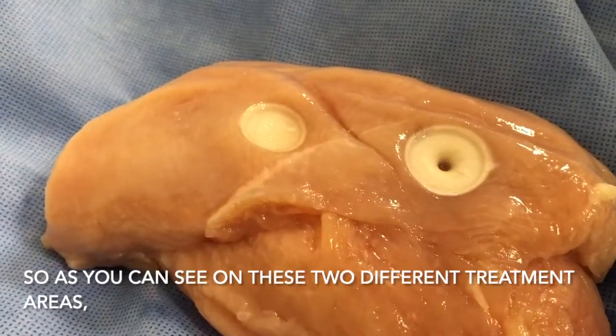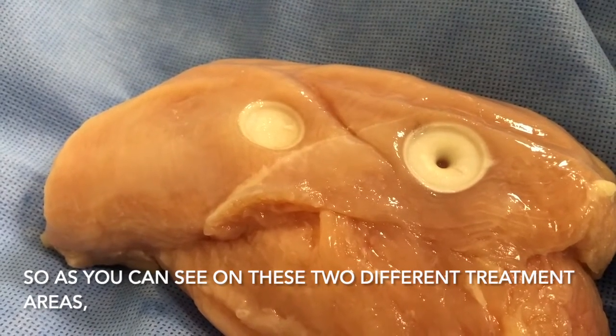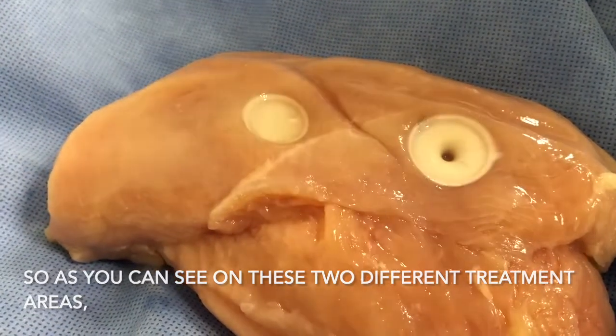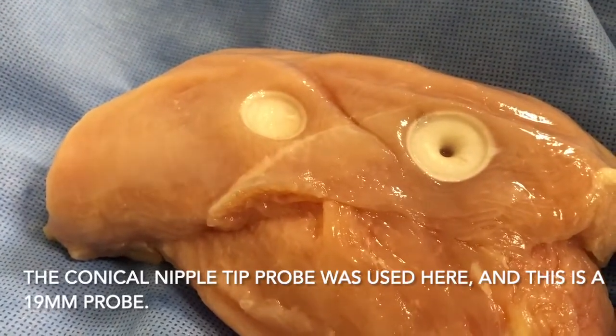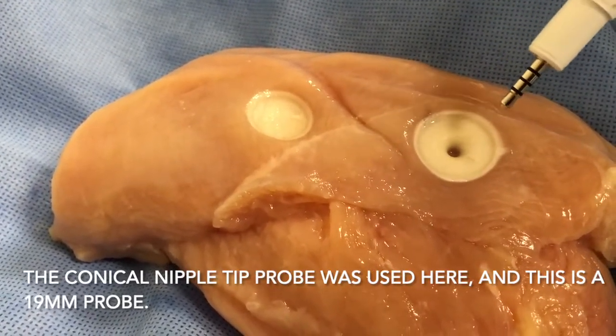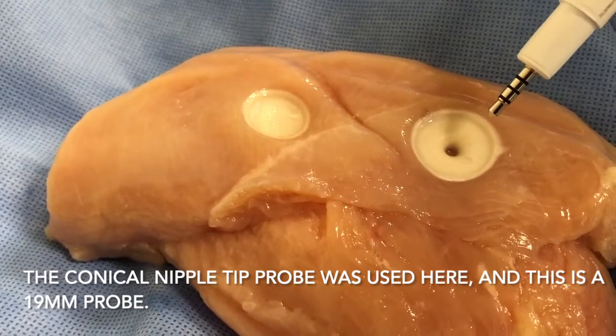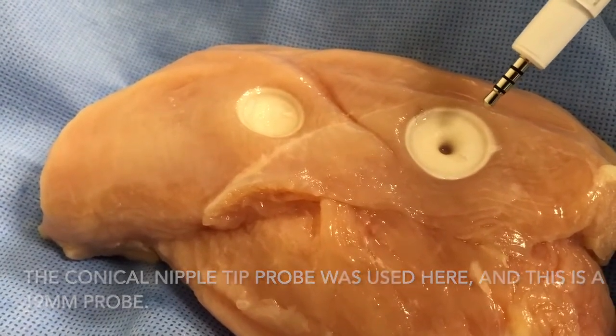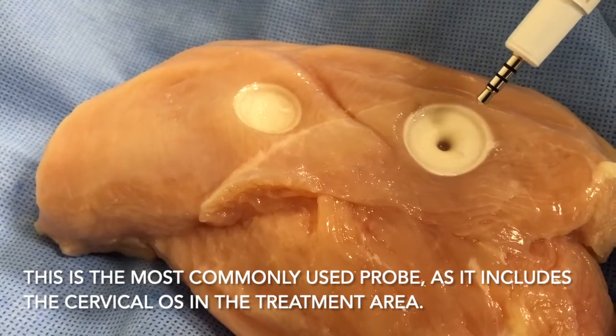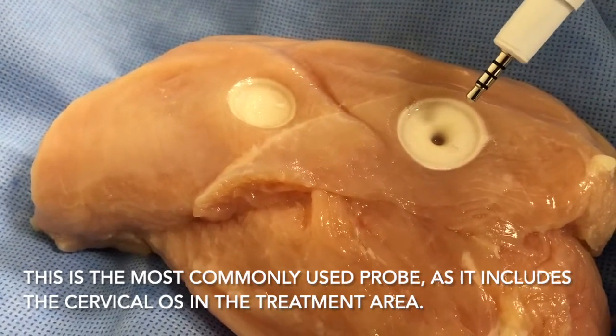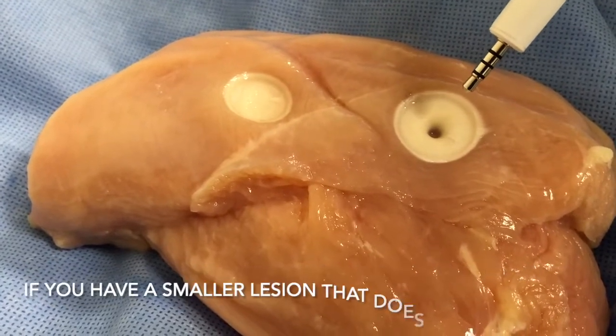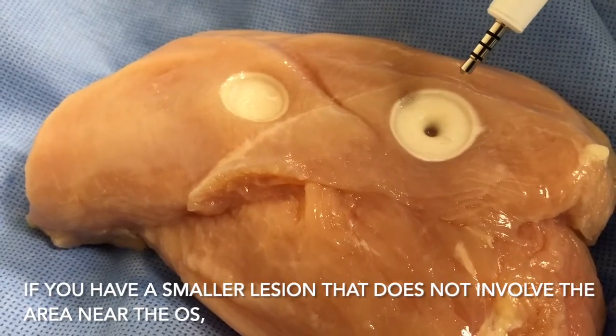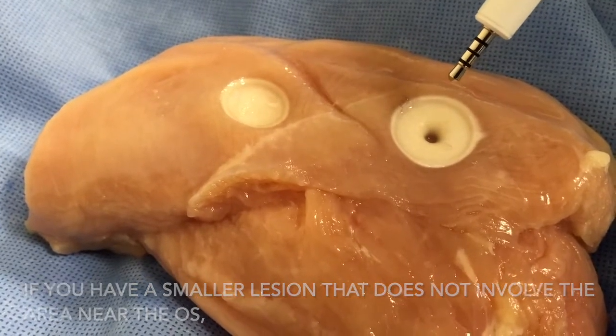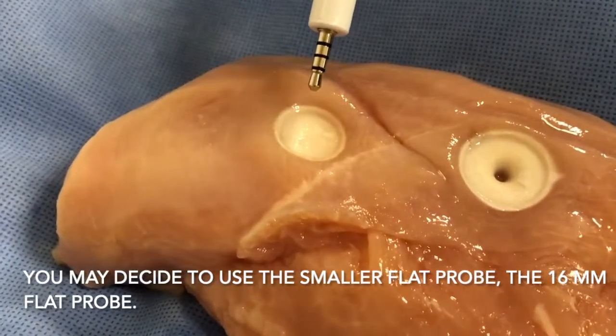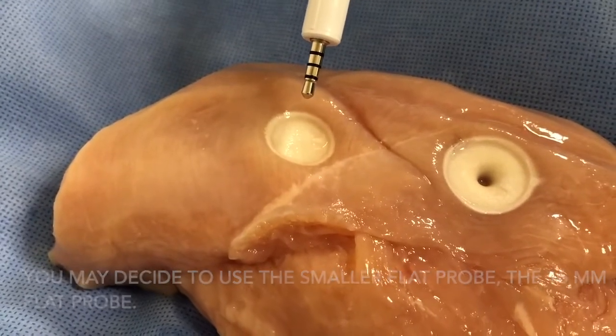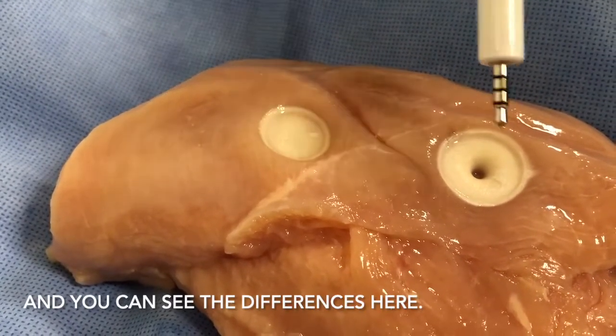So as you can see on these two different treatment areas, the conical nipple tip probe was used here, and this was a 19 millimeter probe. Again, this is the most commonly used probe as it includes the cervical os in the treatment area. If you have a smaller lesion that does not involve the area near the os, you may decide to use the smaller flat probe, the 16 millimeter flat probe. And you can see the differences here.